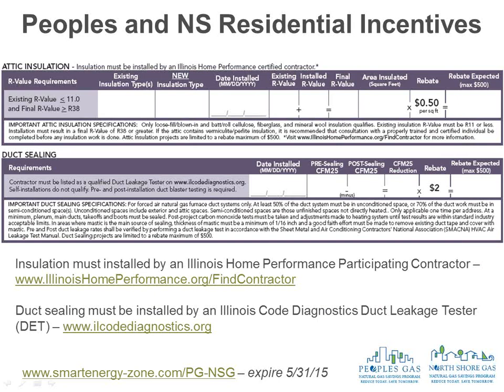So you have to do a pre-test and a post-test, before and after you do the sealing, whether you use mastic or tape or Aeroseal or whatever you're doing. Then however much you reduce the CFM, you multiply that by 2, and that's your rebate, with a maximum of $500. Also, 50% of the duct system has to be in unconditioned space, and the definition of that has changed a little bit: 50% in unconditioned, or 70% in semi-conditioned space, like a basement. So there's a little bit of difference in how that's interpreted.